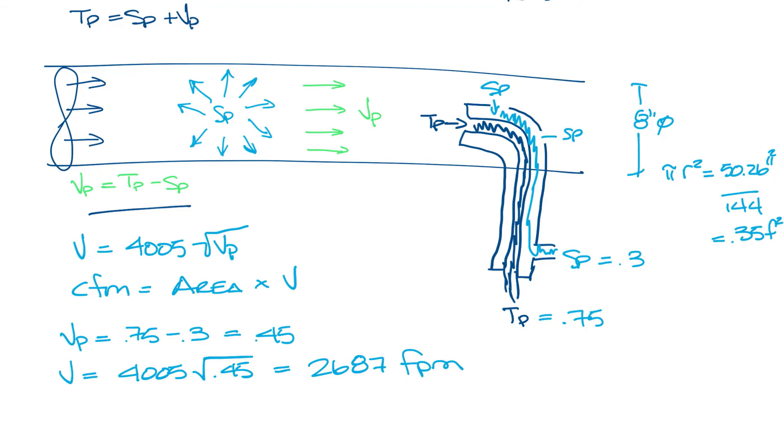So now let's go over here to our CFM equation. CFM equals area, 0.35, times velocity, 2687 feet per minute, and we get a CFM of 940 CFM.